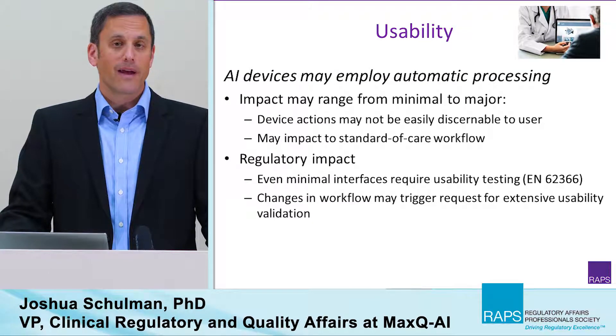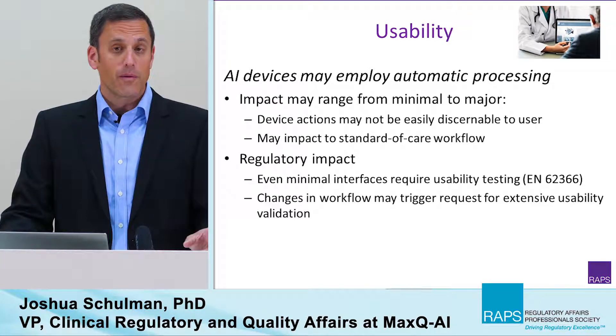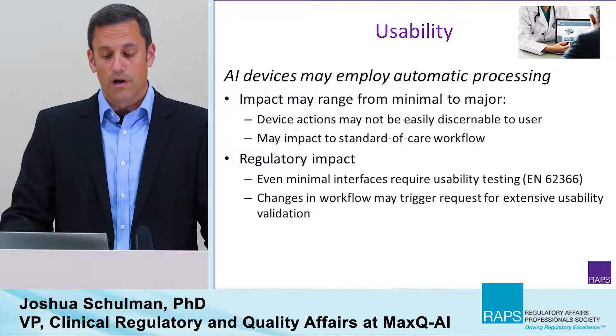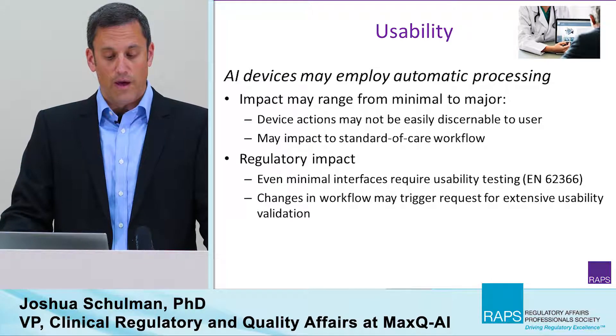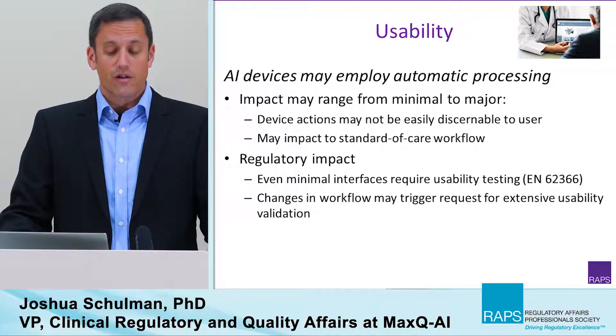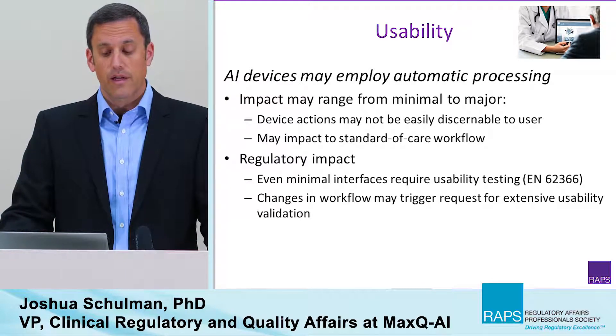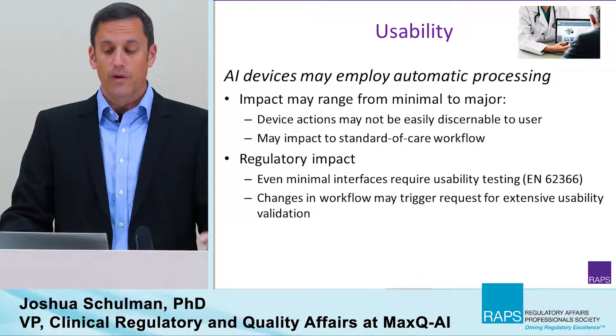One factor that can be overlooked by manufacturers in the development of AI devices is usability. AI devices are often capable of employing automatic processing. The impact of this may range from being minimal to major. On one hand, device actions may not be easily discernible to the user. On the other hand, at the other extreme, they could impact standard of care workflow in a significant way. The regulatory impact is that even minimal interfaces still require usability testing under EN 62366, but at the same time, extensive changes in workflow may trigger requests for substantial usability validation.